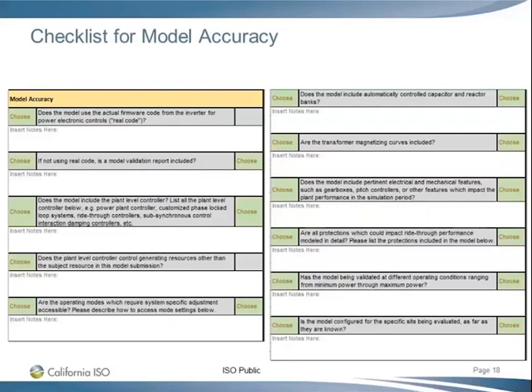So if not using real code, is there a model validation report included? If you do not use real code, we want the model validation. That's when we talk about the benchmarking against measurement, and also benchmarking between the EMT and the positive sequence. And does the model include the plant PPC, plant level controller, and provide a list of all the controllers you have installed in the plant? You should answer yes to this one, otherwise it's not a complete submission.